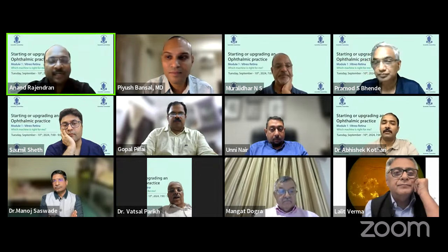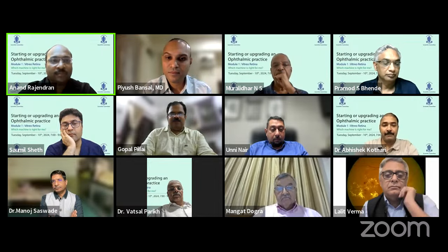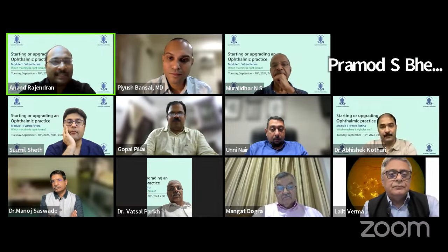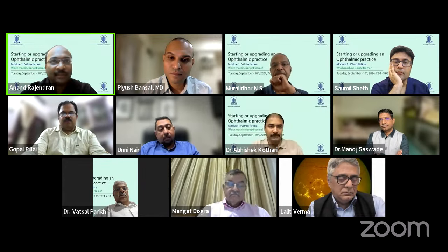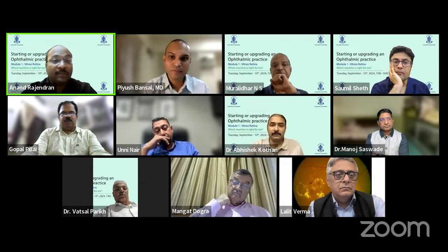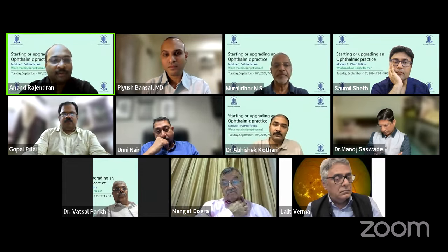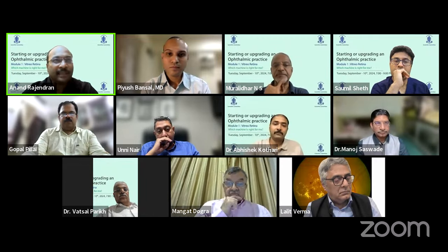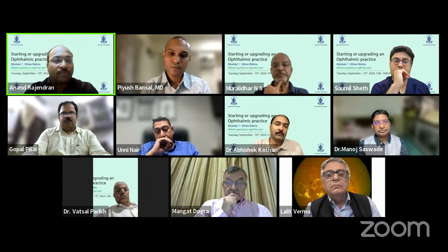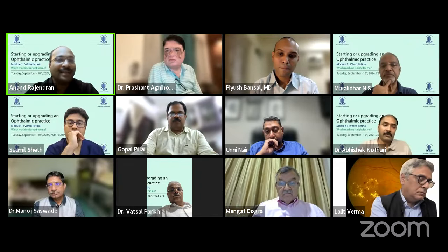Yeah, I'd just like to add, excellent talks by all 3 of them about the vitrectomy machines. I'd just like to add that Abhishek gave a great talk and he spoke about DORC. I endorse that. I use both the Alcon Constellation as well as the Nexus from the DORC systems, and the Nexus is doing a great job. It's just that with the Nexus, if your fluid bottle finishes in the middle of a surgery, especially with a number of surgeries, that priming takes a much longer time.